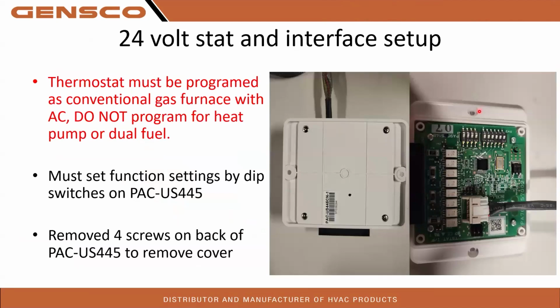So, 24-volt stat interface setup. The thermostat must be programmed as conventional gas furnace with AC. Do not program it for heat pump or dual fuel. I see you guys making this mistake all the time and the system doesn't like it. It doesn't work correctly. So on your thermostat, make sure you program it for either single stage or two-stage gas furnace with AC. We don't want it set up as a heat pump.